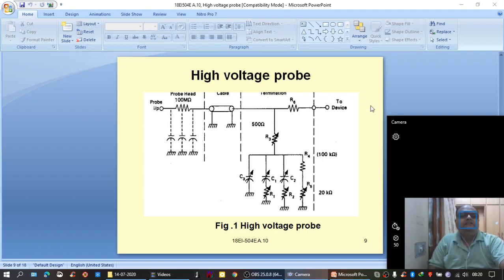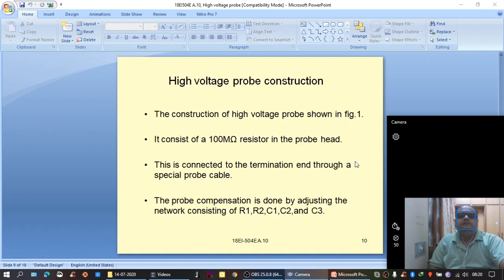100 is to 1, multiply the output of the meter with 100. 1000 is to 1, multiply the output of the meter with 1000. That means, suppose the output indication is 0.2 volts, in the first case, multiply with 10, that is 2 volts. In the second case, multiply with 100, it would be 20. The third case, it would be 200. So that is all about the high voltage probe, and its construction is given here. The construction of a high voltage probe is as shown in figure.